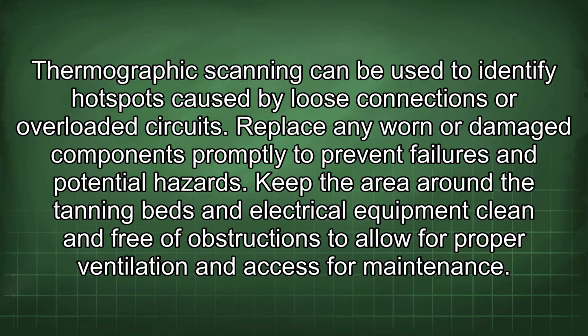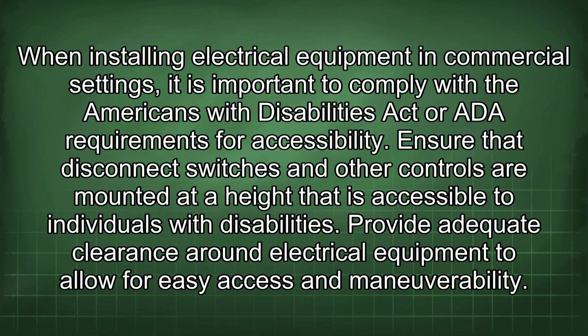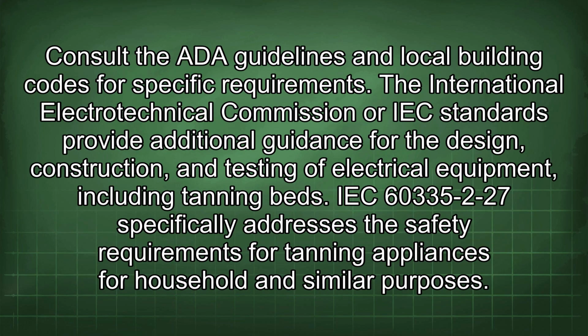Keep the area around the tanning beds and electrical equipment clean and free of obstructions to allow for proper ventilation and access for maintenance. When installing electrical equipment in commercial settings, it is important to comply with the Americans with Disabilities Act, or ADA, requirements for accessibility. Ensure that disconnect switches and other controls are mounted at a height that is accessible to individuals with disabilities. Provide adequate clearance around electrical equipment to allow for easy access and maneuverability. Consult the ADA guidelines and local building codes for specific requirements.